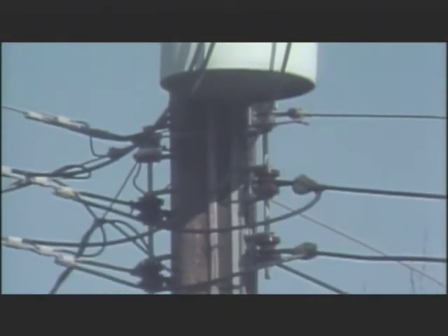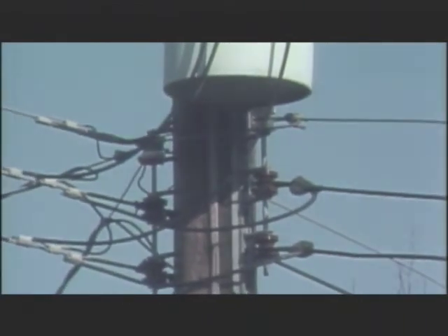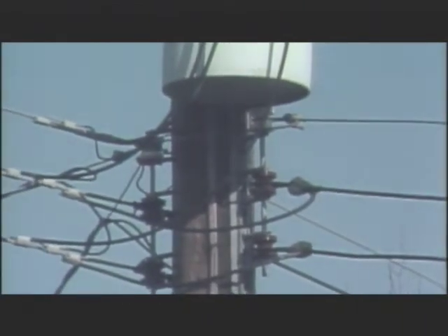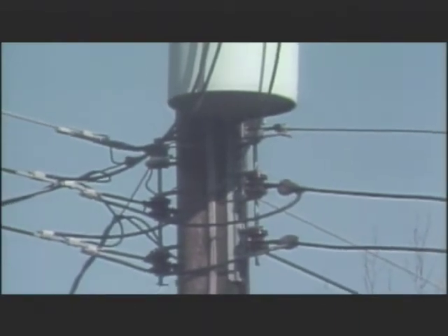Three or more very small bushings are located on the side of each transformer. These are the low-voltage bushings. They're connected to the conductors that carry electricity at the reduced voltage. These conductors are called secondaries. Secondaries are strung between poles below the transformers. Usually, they'll extend one or two poles on either side of a transformer.